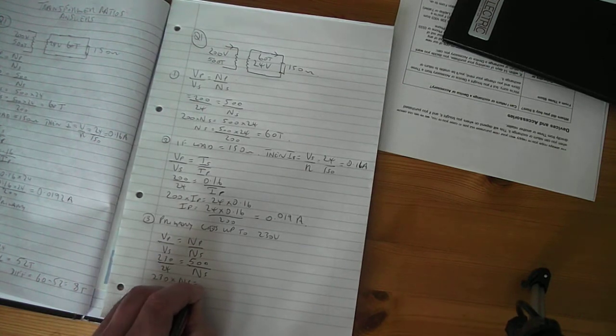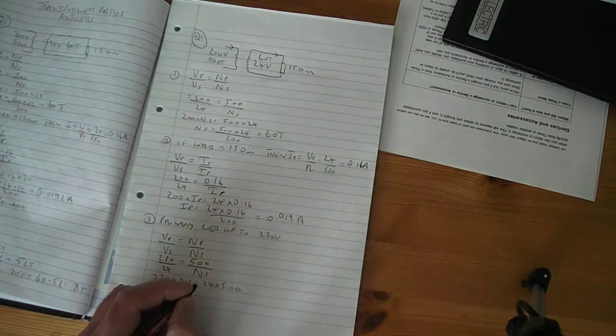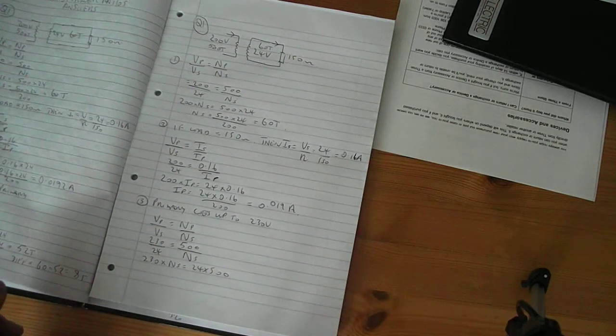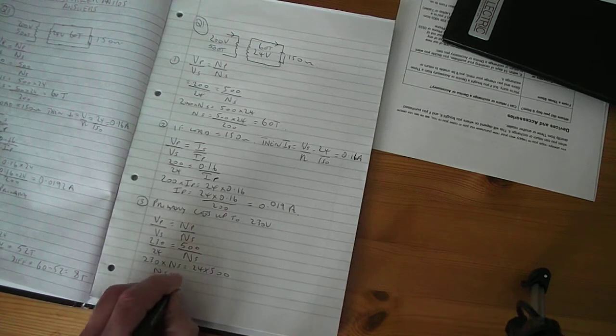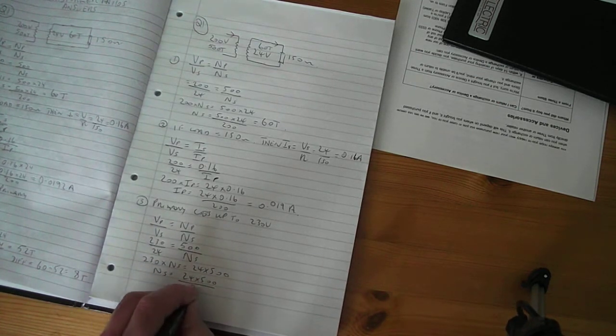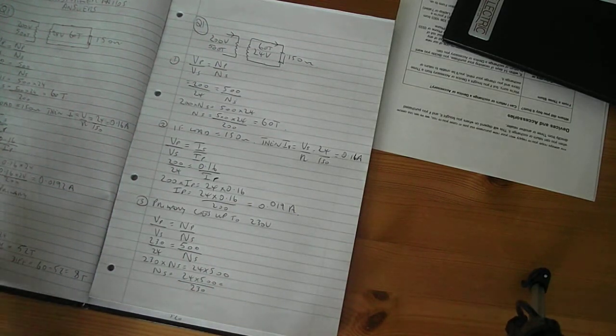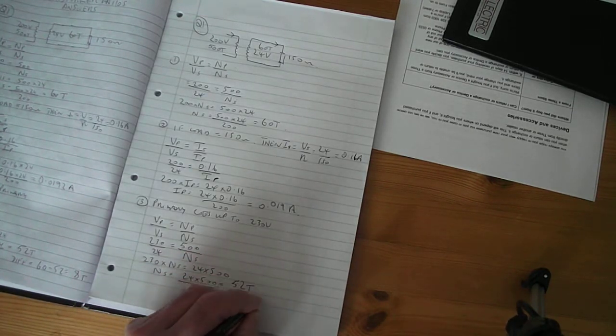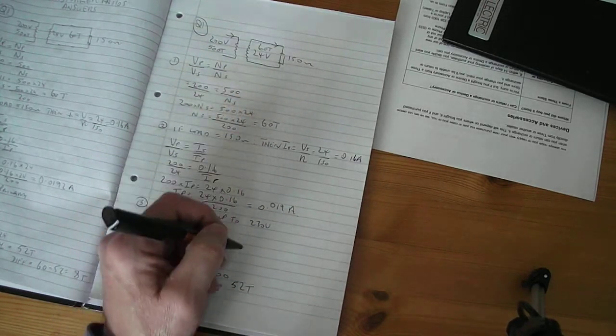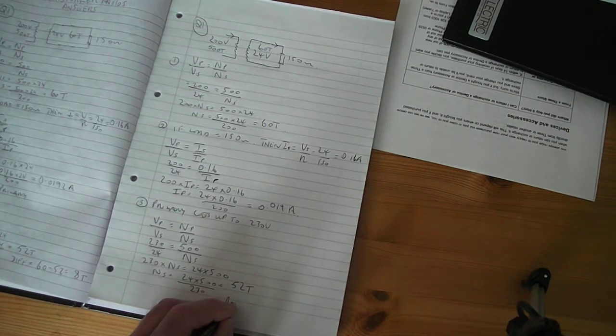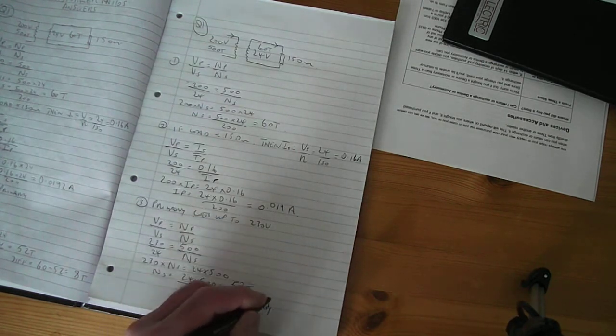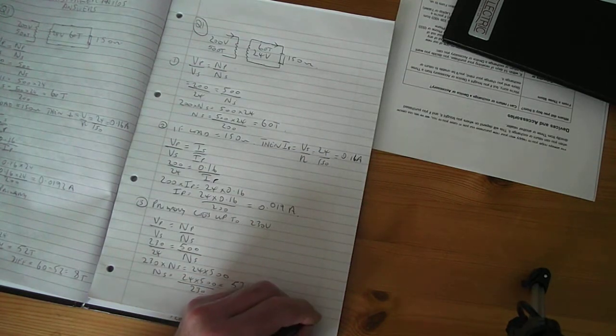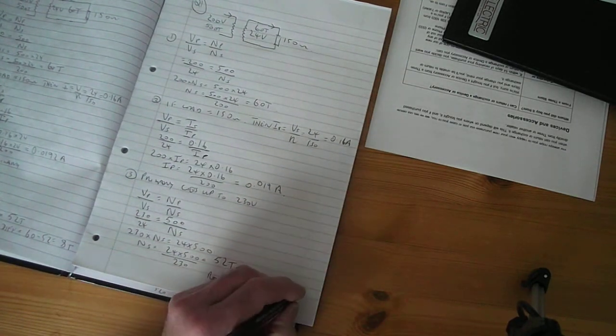Cross multiply. 230 times Ns equals 24 times 500. Can you still see that on there? Just push that up a little bit. So Ns equals 24 times 500 divided by 230 equals 52 turns. So the new turns is 52, the original is 60, so we need to reduce it by 60 minus 52 turns equals 8 turns.